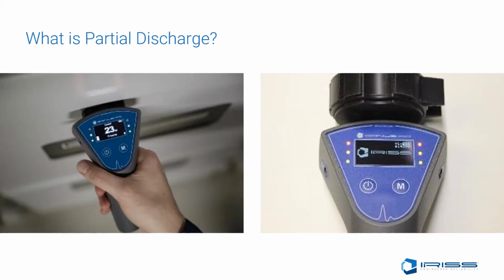Defects on the surface of a high voltage insulator are prone to phenomena known as treeing and tracking. These cause carbon deposits to build up over time, ultimately leading to flashover and insulation failure. The partial discharge detection device is highly sensitive to TEV and ultrasonic emissions produced by these events and can find the incipient stages of partial discharge events before a phase-to-phase and phase-to-ground event can occur. As the insulation value around the anomaly breaks down, the magnitude and number of pulses increases dramatically, and over a 6-month period, this could easily double and lead to faster end of useful life for the gear.